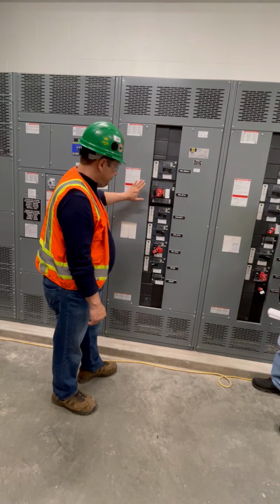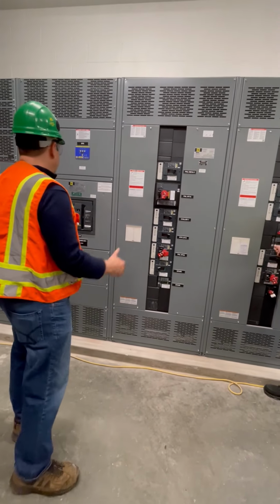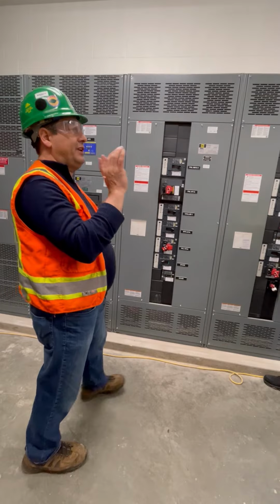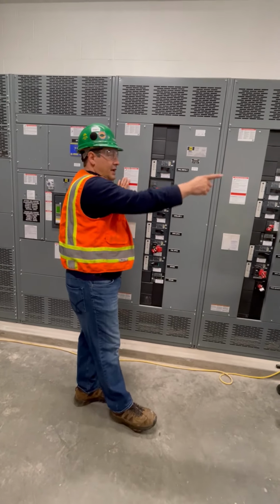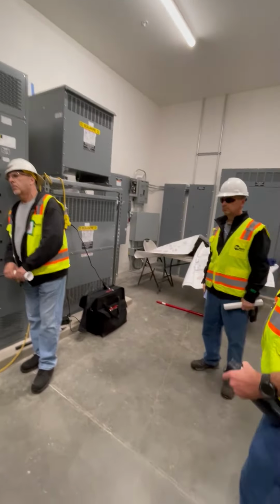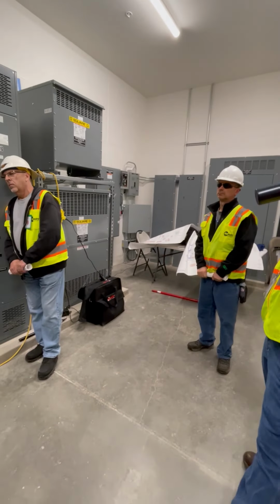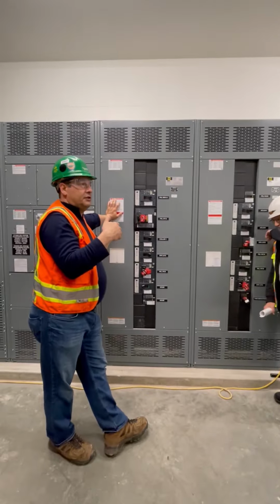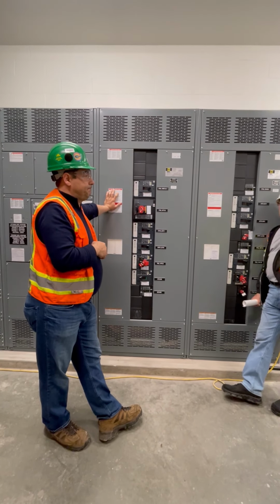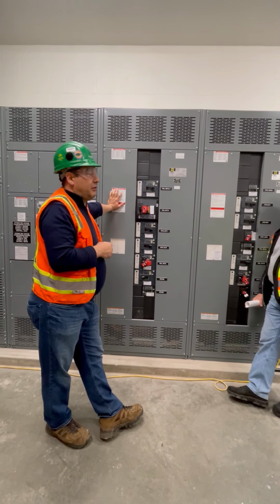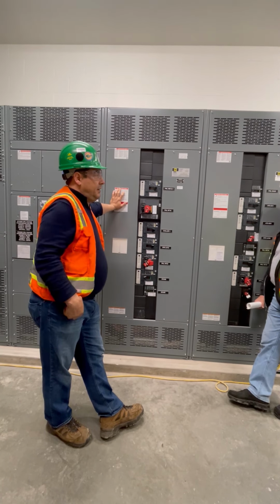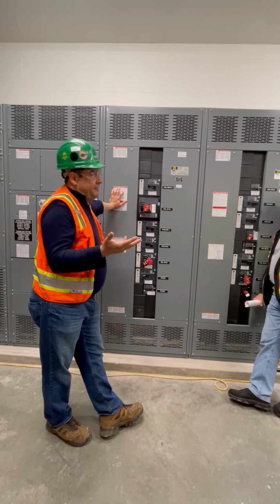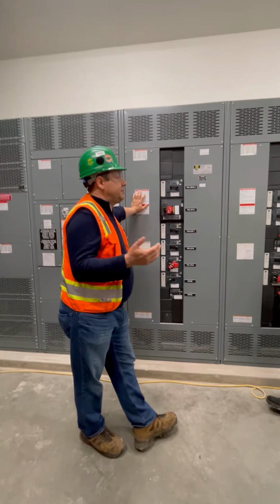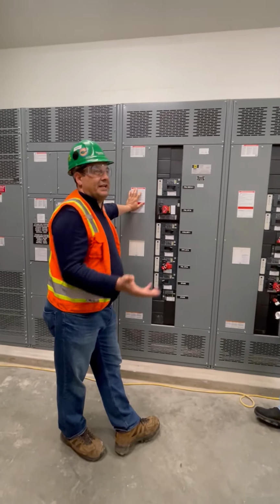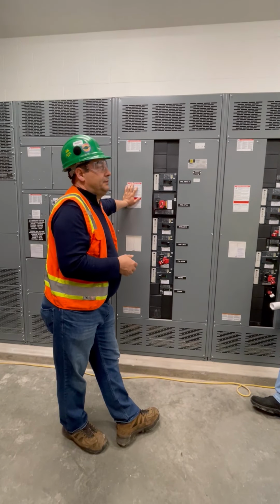And I don't see that you have anything else, so that kind of covers the maintenance on it. And really, when you go downstream, right? Obviously, this is a big switchboard, and on panel boards it's the same concept, right? If you look at maintenance, check torque, check connections. I don't know if you've developed an IR program, but one of the most common events with switchboards, panel boards, and so on, is loose connections over time, right? So that's why the maintenance is intended to check connections.